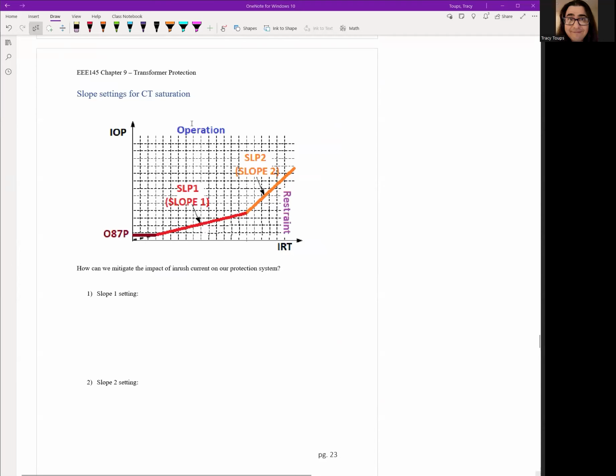Okay. So how do we stop CT saturation from inadvertently triggering the 87 differential? Well, we could use the restraint settings. So remember, we had restraint settings for the CT mismatch. This is what they call slope. So slope is very similar to restraint. Right. So for the restraint setting, they say 15%. Some relays just say a slope of 15%. But a slope is literally the y equals mx plus b line of the restraint itself.